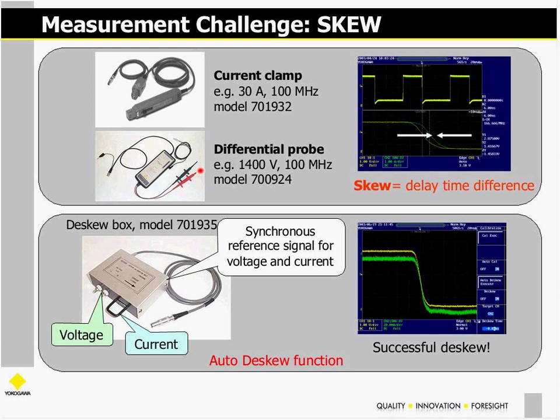What I mean by that is you can avoid creating ground loops. If I was using a passive probe and I connect the ground lead to it, I've now grounded the scope, which is already grounded to the grid. I've now grounded my switch mode power supply and my scope together back to the grid. So I've created a ground loop there that typically will offer a place for currents to flow out of the switch mode supply ground plane back into the grid ground line, and vice versa. So what you end up with is noise, and it affects your measurement.